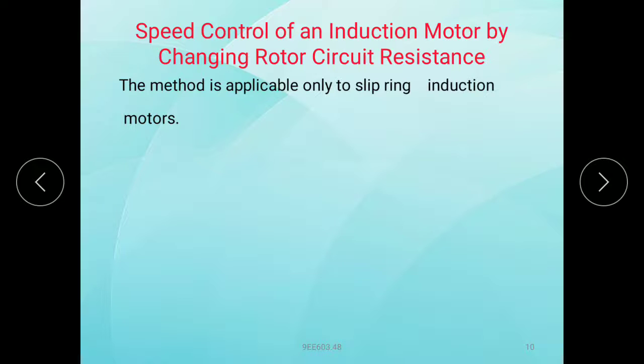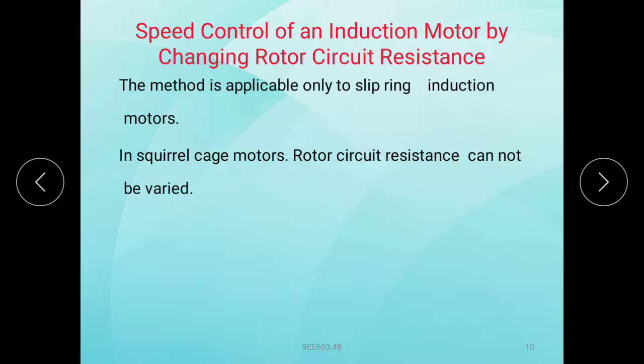The method is applicable only to slip ring induction motors. Very important. In squirrel cage motors, rotor circuit resistance cannot be varied.